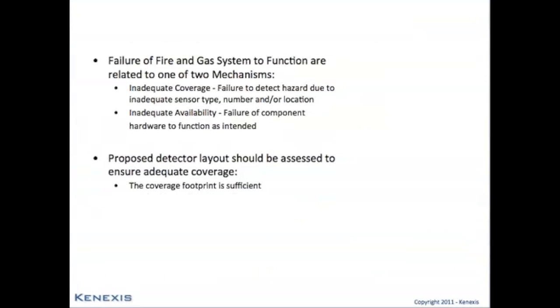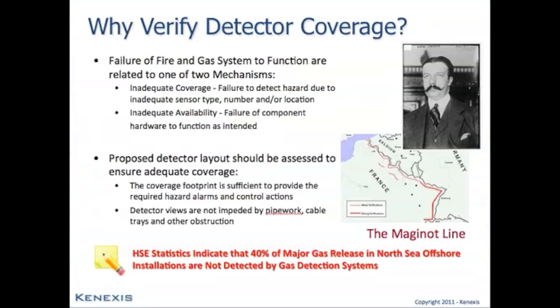The new feature that's included in the ISA 84.00.07 technical report that is not included in the ISA 84 or the IEC 61511 standard is the addition of coverage as a performance metric that must be achieved in addition to the safety availability, which again is related to the safety integrity level, or SIL, of a safety instrumented function. One might ask, why is verifying detector coverage important? Why can't we just use safety integrity level alone as the single metric that the basis of safety is based on?